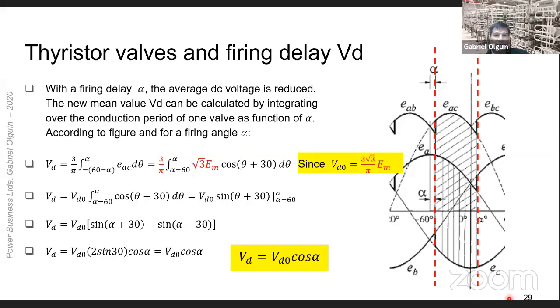Okay, let's now introduce the firing delay or the ignition control. HVDC uses a thyristor valve, which allows us to introduce a delay in the ignition instant of the valve. This ignition delay is known as gate control. The gate control allows us to delay the firing of the valve. The delay angle is denoted alpha and corresponds to a delay of alpha divided by omega seconds. With delay, valve 3 ignites when omega t equals alpha instead of omega t equals 0. Valve 4 ignites when omega t equals alpha plus 60 degrees, valve 5 when omega t equals alpha plus 120 degrees, and so on.